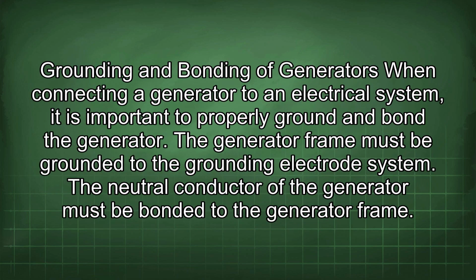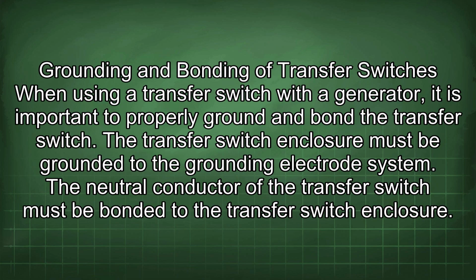Grounding and bonding of generators. When connecting a generator to an electrical system, it is important to properly ground and bond the generator. The generator frame must be grounded to the grounding electrode system. The neutral conductor of the generator must be bonded to the generator frame. Grounding and bonding of transfer switches. When using a transfer switch with a generator, it is important to properly ground and bond the transfer switch. The transfer switch enclosure must be grounded to the grounding electrode system. The neutral conductor of the transfer switch must be bonded to the transfer switch enclosure.